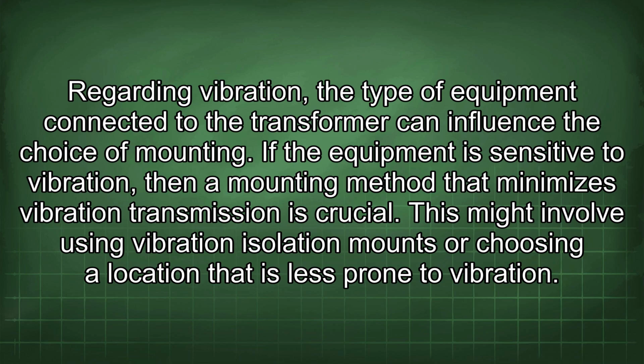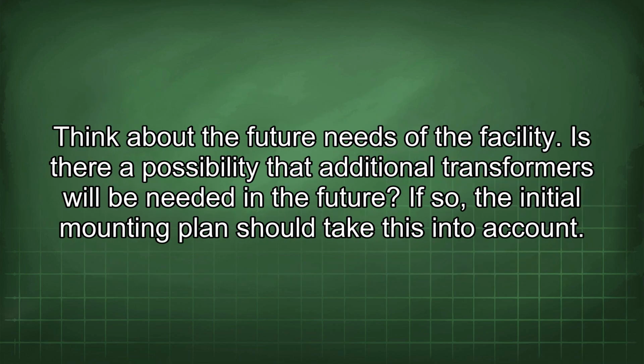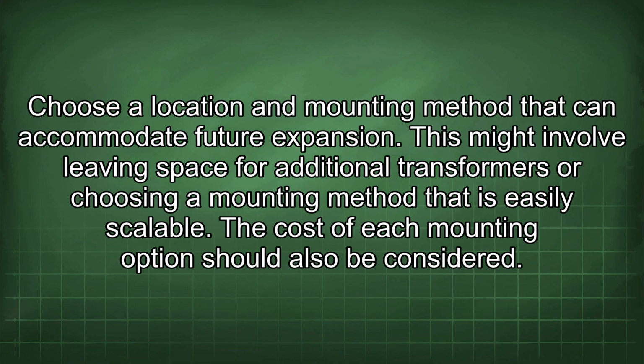Regarding vibration, the type of equipment connected to the transformer can influence the choice of mounting. If the equipment is sensitive to vibration, then a mounting method that minimizes vibration transmission is crucial. This might involve using vibration isolation mounts or choosing a location that is less prone to vibration. Think about the future needs of the facility. Is there a possibility that additional transformers will be needed in the future? If so, the initial mounting plan should take this into account. Choose a location and mounting method that can accommodate future expansion. This might involve leaving space for additional transformers or choosing a mounting method that is easily scalable.